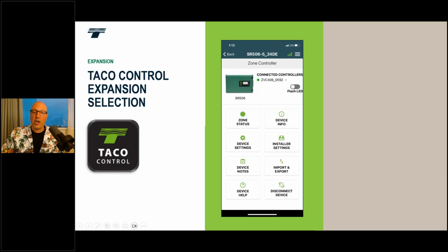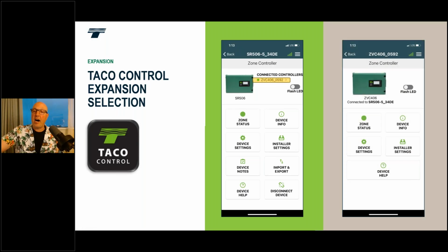I can click on right there on where it says ZVC, and I pop up and I can see my ZVC. That is my expansion terminal, my expansion board, and this one is my master board. You'll see you have a couple more, like the import export setting is not available on the expanded one, because it's going to be on the master board, downloading and give you all the settings onto your device from back and forth that way.